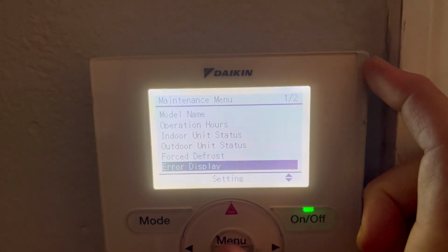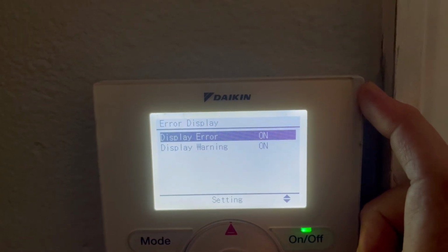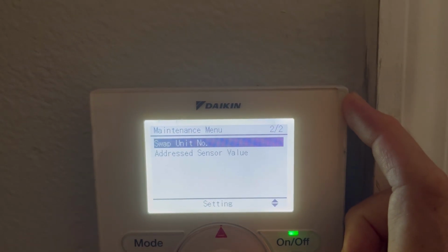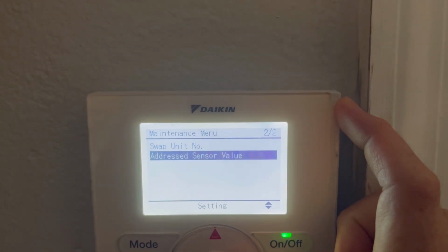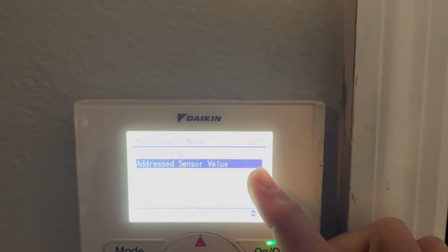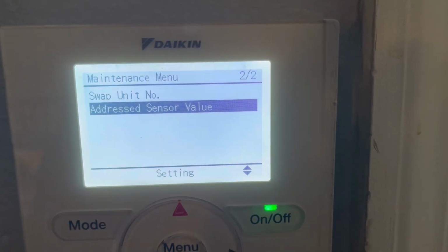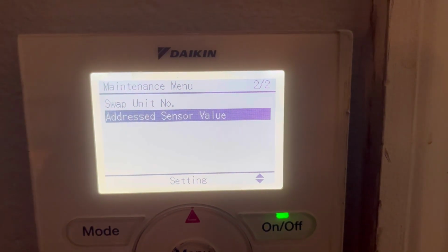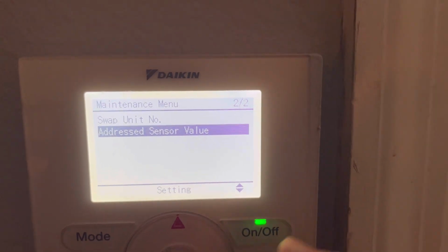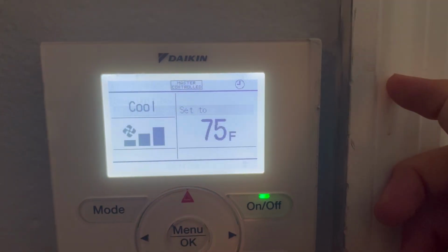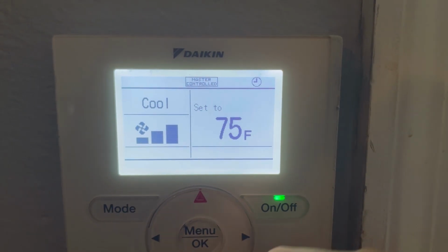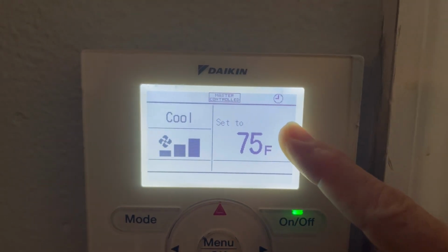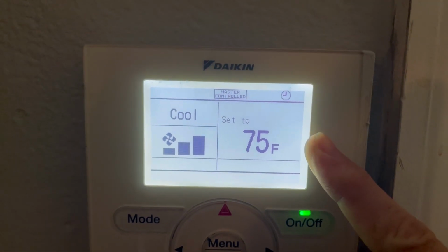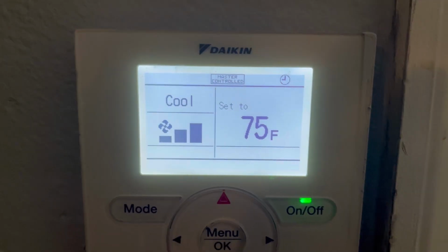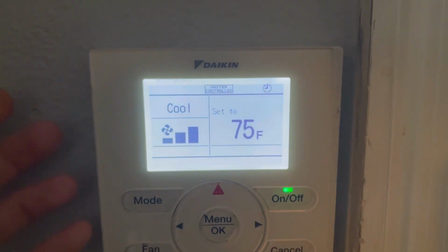Force defrost, error display, right? You can have warnings display, you can have errors display, swap unit number, and then address sensor value. That's something you would use on older units that don't actually register in that maintenance menu for indoor unit status. Not something I'm going to cover today, but again, these are your 2 menus that you have access to, not only just your service settings, but also your maintenance menu settings, which allow you to see things in greater detail. When do you use them? Why do you use them?